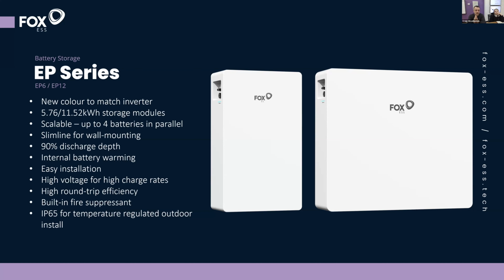These can be paralleled in the same way—you can parallel through our junction box up to 4 units in parallel. As with the EP5 and EP11, you can't mix these; you parallel the same units. That parallel junction box will be made available in the same coloring as these new battery versions. It's still IP65, still has built-in fire suppressant, still has internal battery warming—everything else is the same.